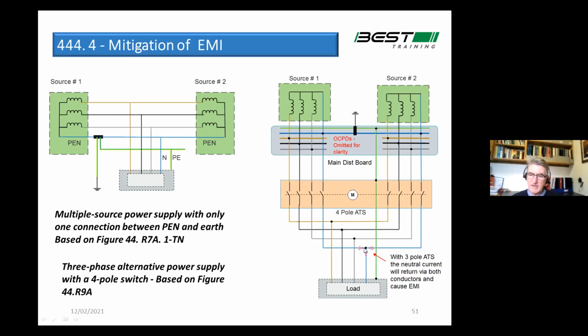When the neutral current comes back here, it can split up both ways and go back through the A path and go back through the B path. So only the A path is live. So that cable is out of balance because it's not carrying all its neutral current. And this one's definitely out of balance because it only has current flowing through the neutral conductor. So that stray current flowing through there is out of balance, and it causes a magnetic field to be set up around the cable. And that fluctuating magnetic field at 50 hertz can induce voltages into nearby signal cables and corrupt the data or do other damage. So that's really the thinking behind that.